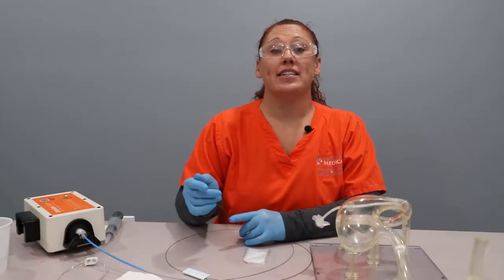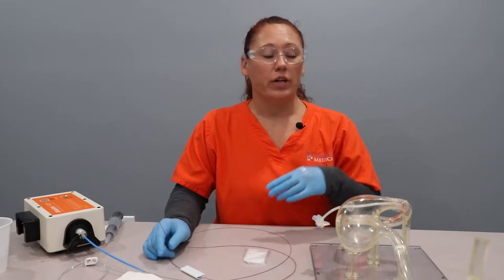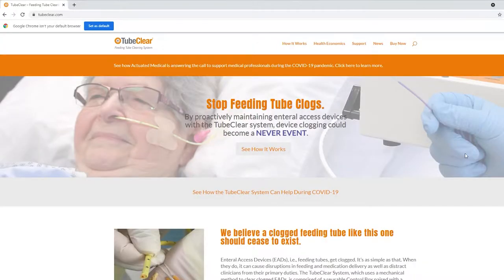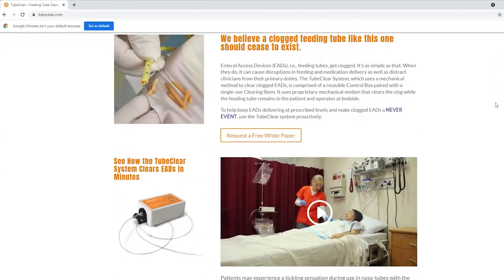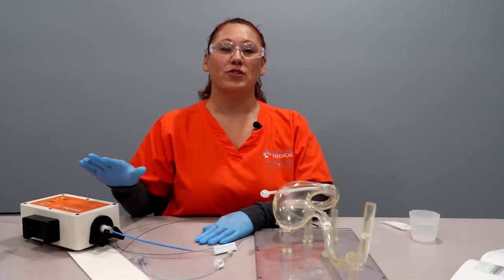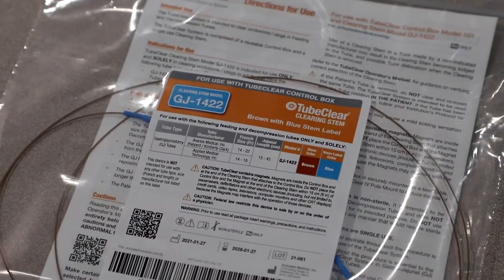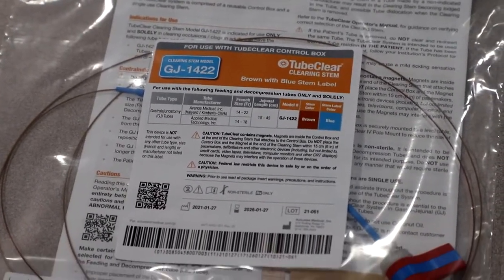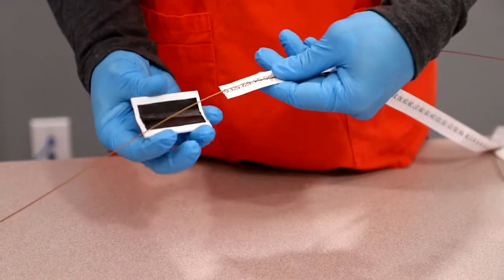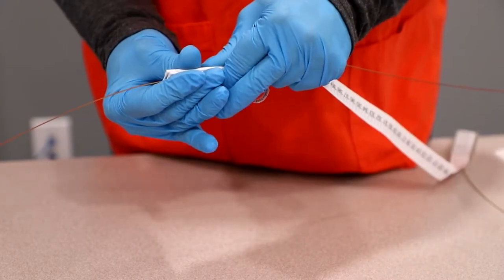For instructions on how to set up the control box or the GJ1422 Clearing Stem, please refer to your operator's manual or the helpful videos on our website at www.tubeclear.com. Today we're here to show you how to use the TubeClear System with the GJ1422 Clearing Stem to clear a MIC-KEY gastro-jejunal feeding tube. For the purpose of this video, I have already set my depth limiter as per the instructions located in the operator's manual.